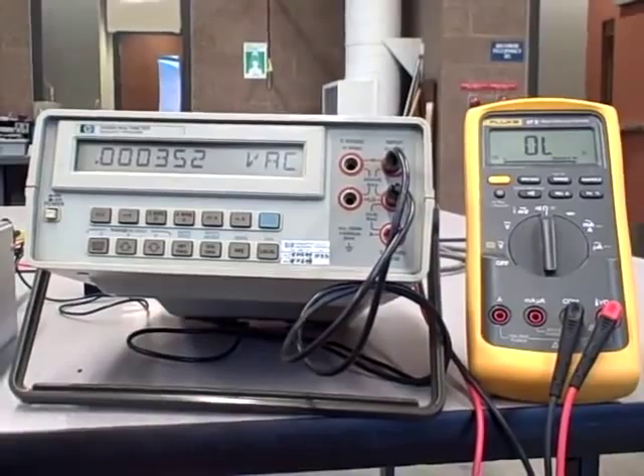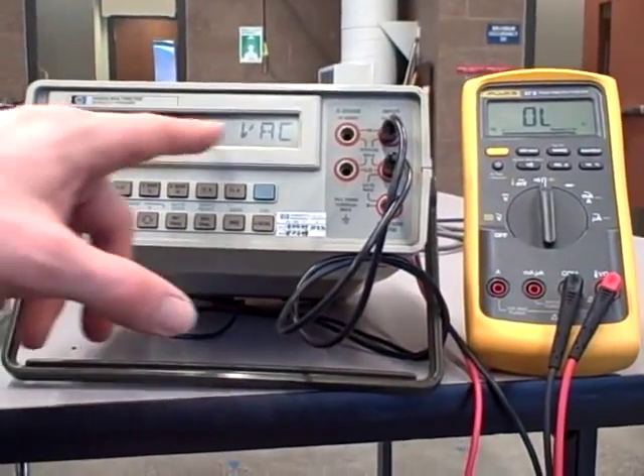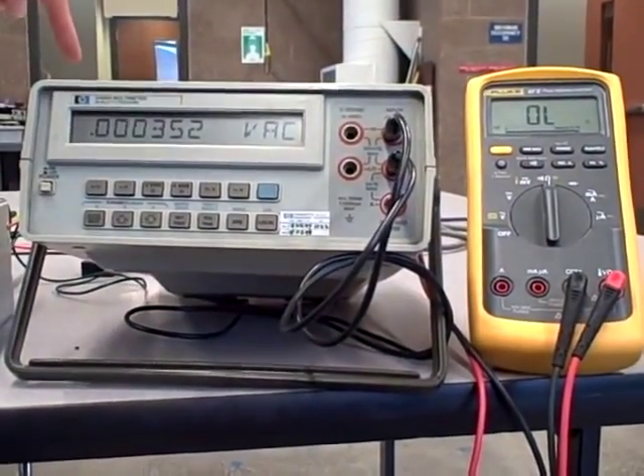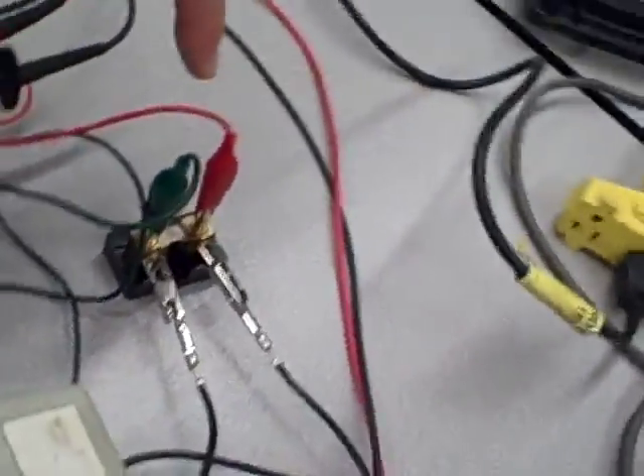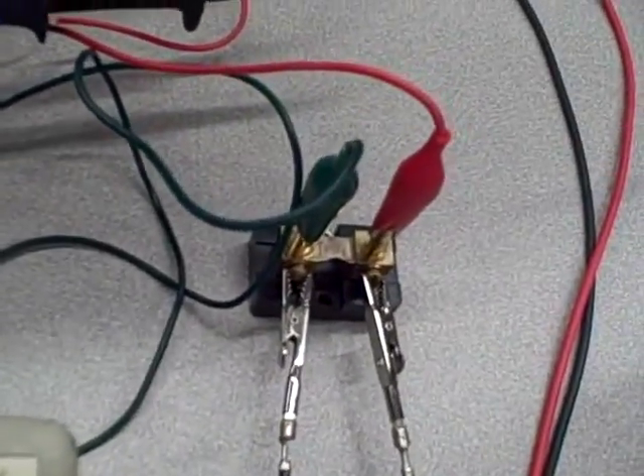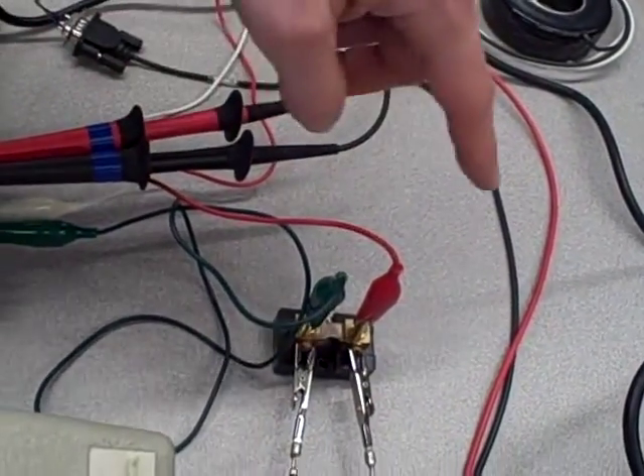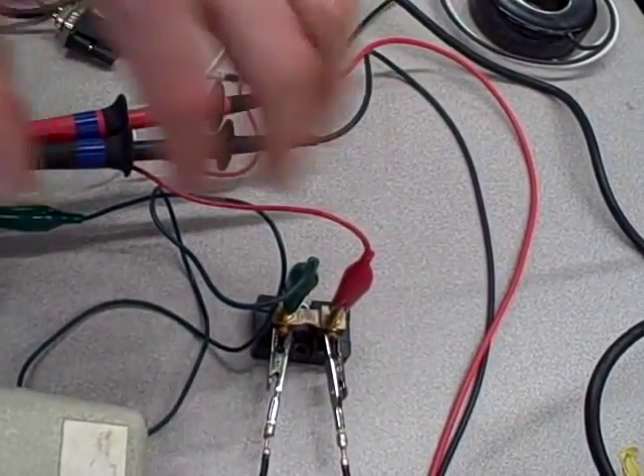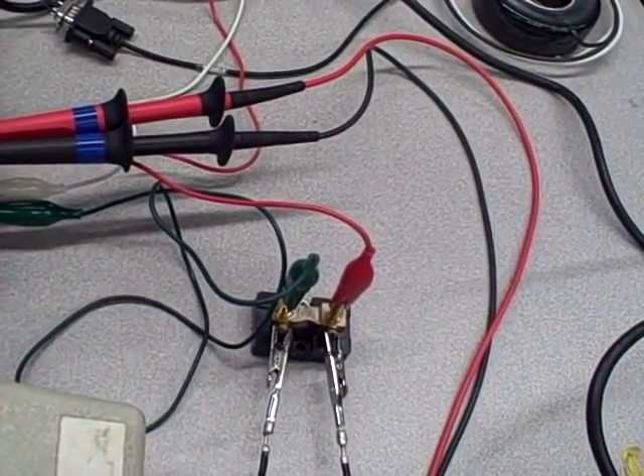To monitor what's going on, we have a meter here, which is going to measure how much current I put into the device. We're measuring volts AC over a shunt resistor. So we'll pan the camera over here. This is a 1 milliohm shunt resistor measuring the amount of current that I have going through the relay. And so with 1 amp of current going through, I get 1 millivolt of drop. And this permits me to measure fairly high currents with this meter.